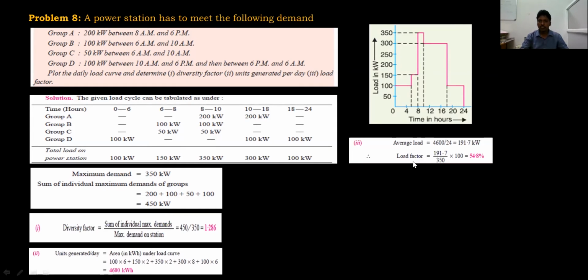Average load factor is equal to average load divided by maximum demand, that is 191.7 divided by 350. That gives you 54.8 percent.